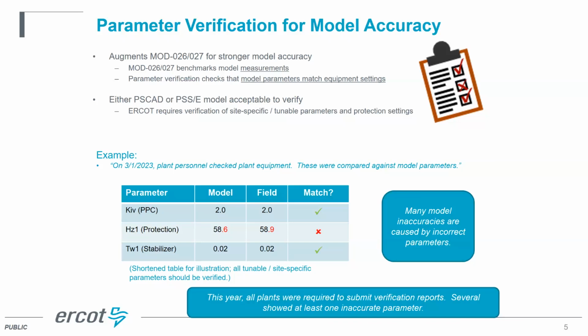This augments the MOD 2627 studies. Those studies are test measurement based. This is a numerical comparison, and so it goes a lot further than the MOD studies because those typically don't run fault response or large signal response. They're kind of limited in what they can do for IBRs. They also don't typically check protection settings or exciter limiter settings. So this is where we get into more detail with parameter verification.